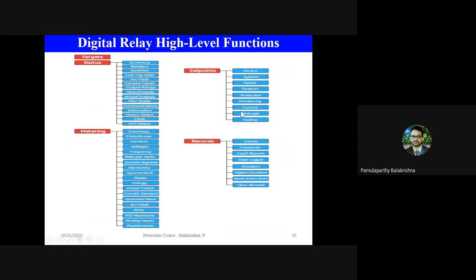So these are basically configuration inputs given by the operator in order to define how the protection relay has to work. Okay, so the fourth and last major high-level function is the records. As I told you, the major purpose of the digital protection relay is to protect the asset when there are critical faults in the system. As you know, faults in the power system occur in a transient manner and just come and go in a very quick snapshot of time. So it is very difficult for the operator to look at exactly what has happened during the fault.